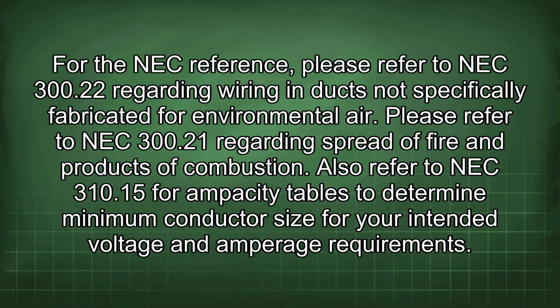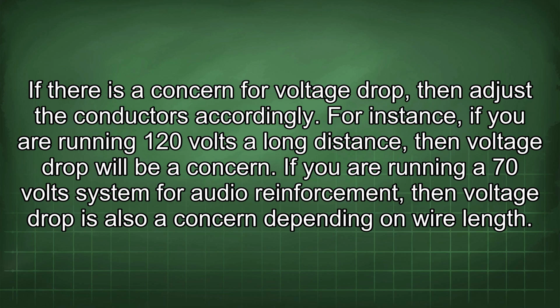For the NEC reference, please refer to NEC 300.22 regarding wiring in ducts not specifically fabricated for environmental air. Please refer to NEC 300.21 regarding spread of fire and products of combustion. Also refer to NEC 310.15 for ampacity tables to determine minimum conductor size for your intended voltage and amperage requirements. If there is a concern for voltage drop, then adjust the conductors accordingly.